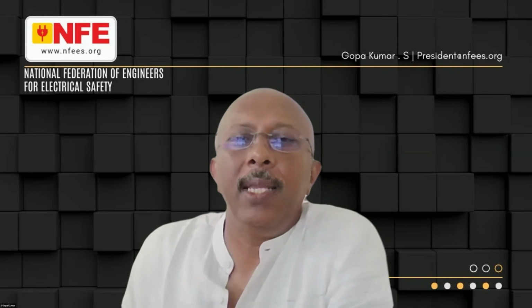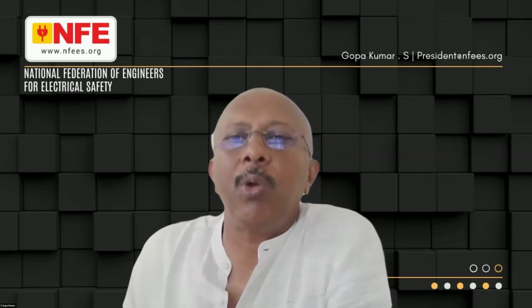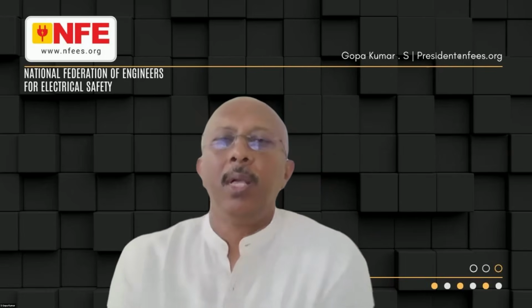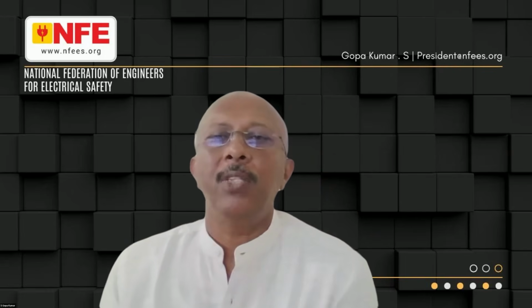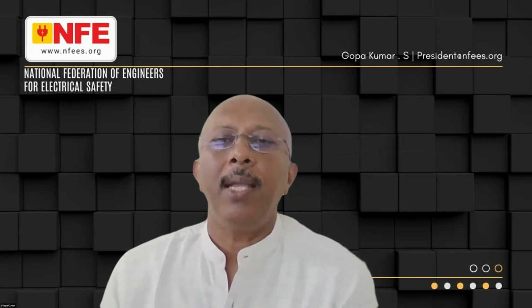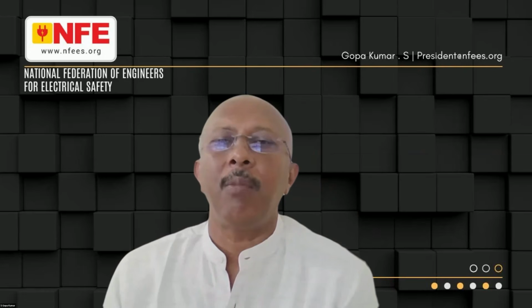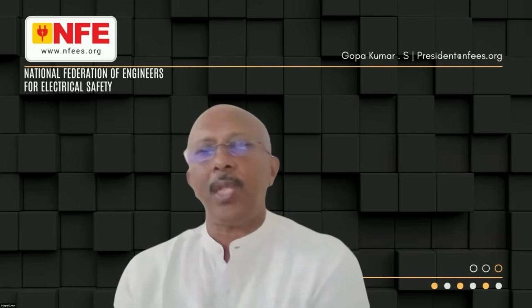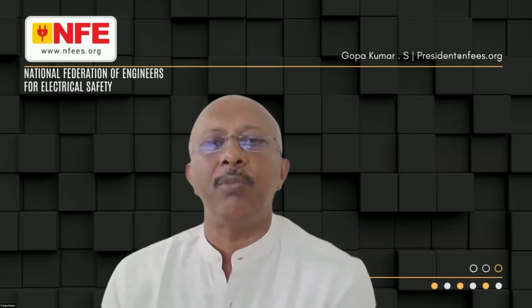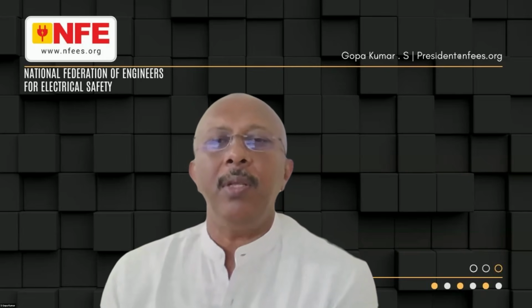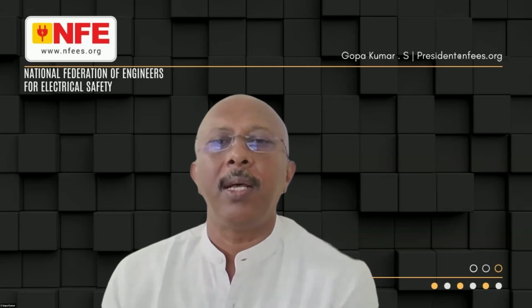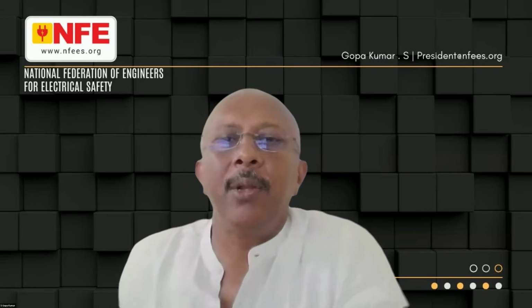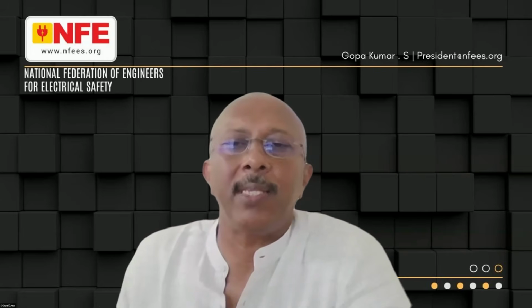So, the next question, Mr. Balasubramani: if the source transformer is located more than 200 meters away from the building or load, and heavy motor-driven equipment such as chillers with compressors are installed, we have observed high leakage current during motor starting, with the chiller body experiencing approximately 60 amps of leakage current. What is the appropriate technical solution, particularly with respect to the earthing system, to mitigate this issue? Oh, this is actually a challenge which most modern equipment has, because the modern electronics, operating with semiconductors, have a filtering system at the beginning, and during starting of the filtering system, of course, there is a large amount of leakage current flowing.